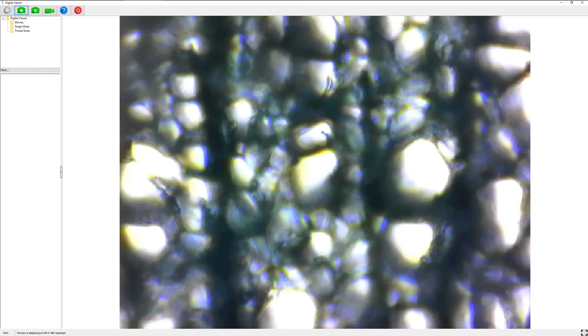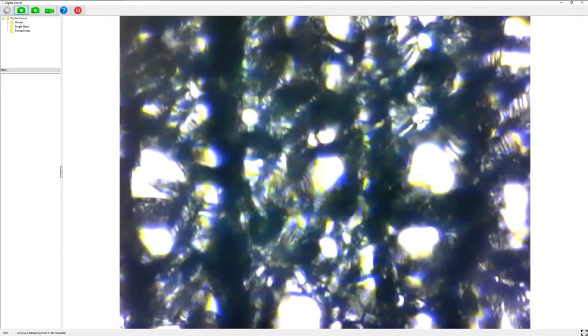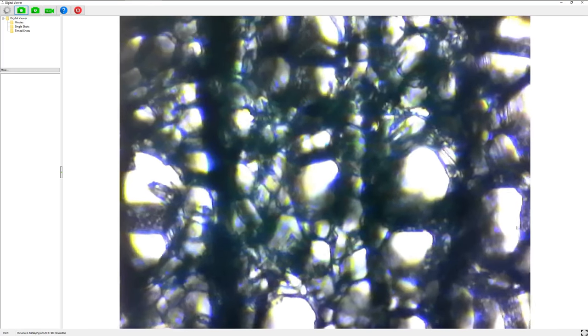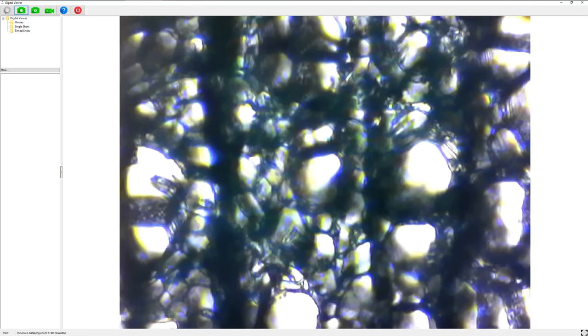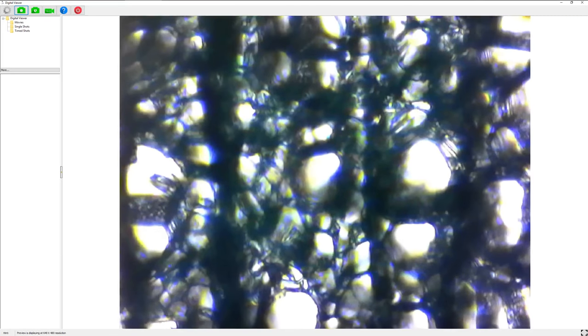I also know why 800x is the kind of limit they've gone to here. Typically if you want to go up to 1000x — the actual limit for light microscopes where you can resolve diatoms — you need oil immersion against the lens, which is an issue of white light. Without messing around with oil immersion and without adding extra cost of different lens magnifications like 4x, 10x, 20x, 40x, 80x, and 100x oil immersion, 800x is a reasonable choice.